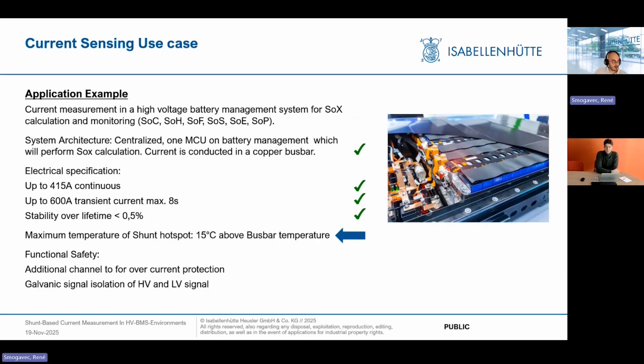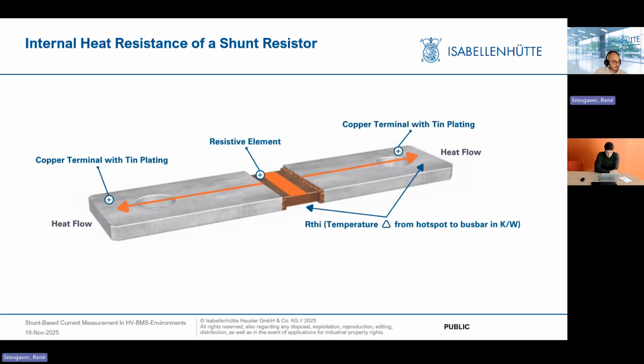Check on that. And the other one, which is important, is the maximum temperature of shunt hotspot. So as said, 15 degrees Celsius, we have 170 max, meaning the maximum terminal temperature must be 155 degrees Celsius hot, which gives us the 15 degrees Celsius of headroom. The 15 degrees is a sum of what the terminal temperature is and the hotspot, which is exactly in the middle of the shunt resistor. And we have a value that's called RTHI, the thermal resistance, that describes this delta.